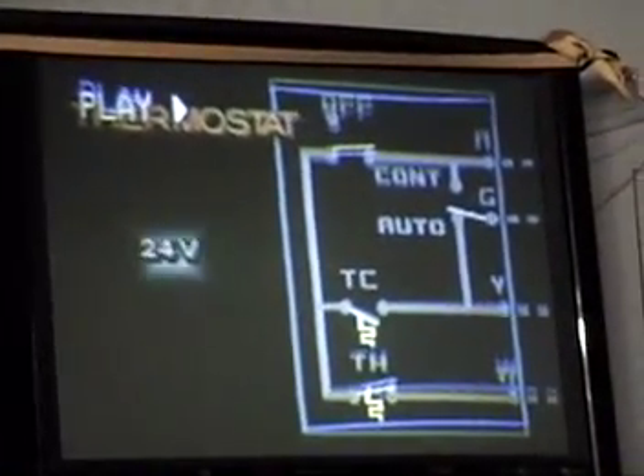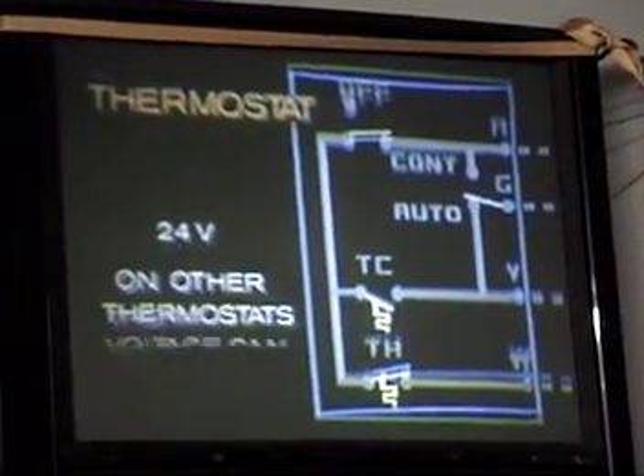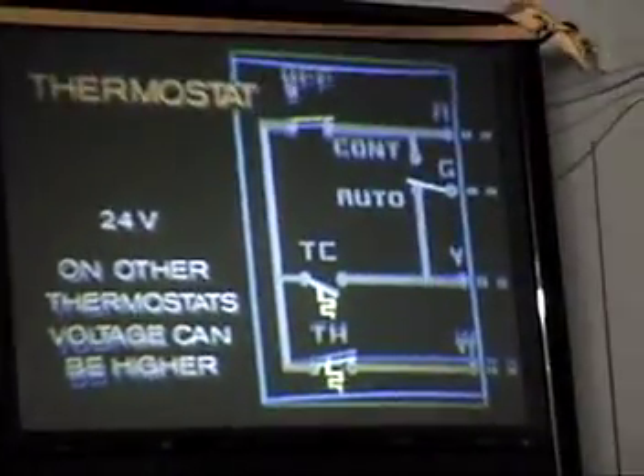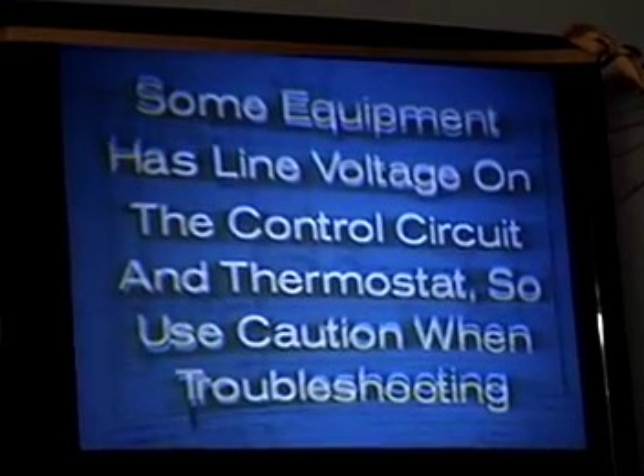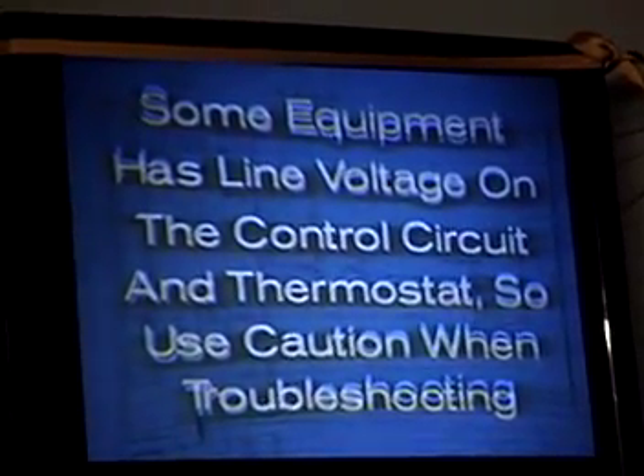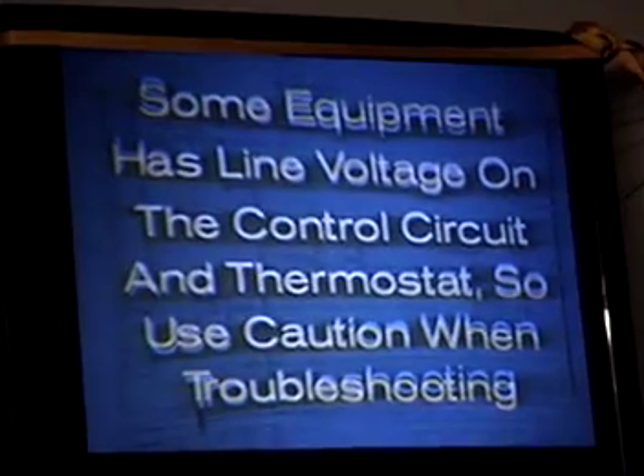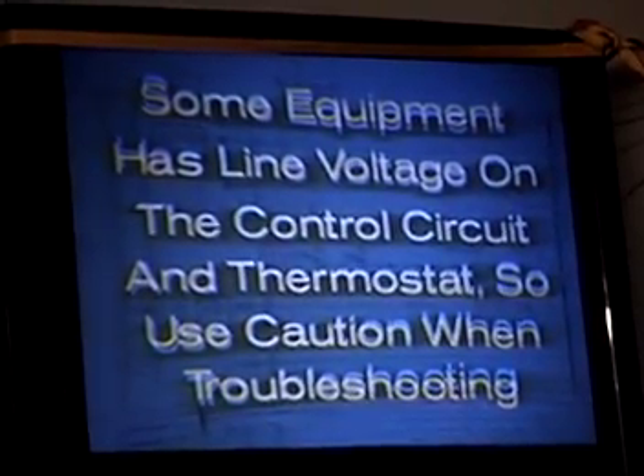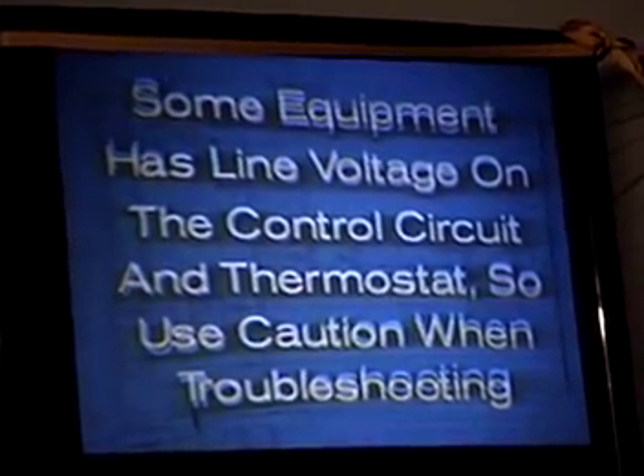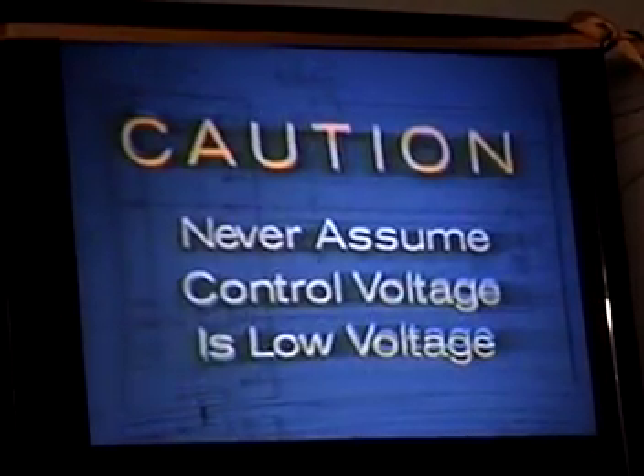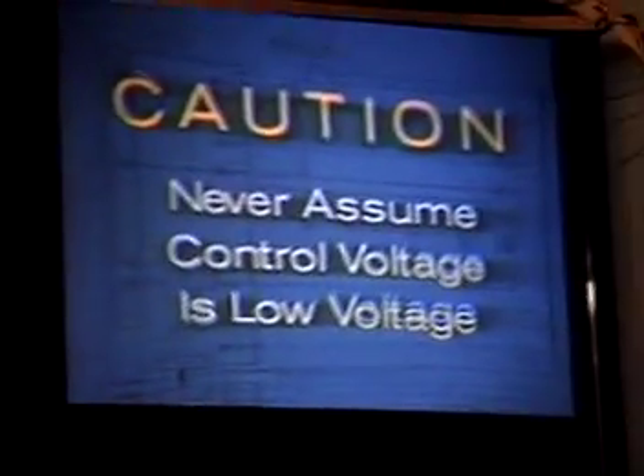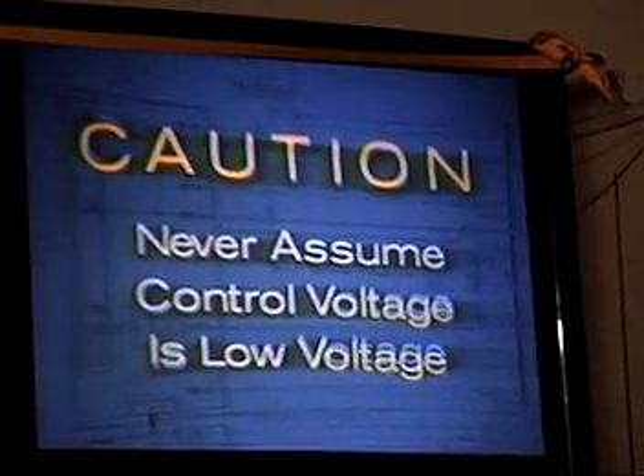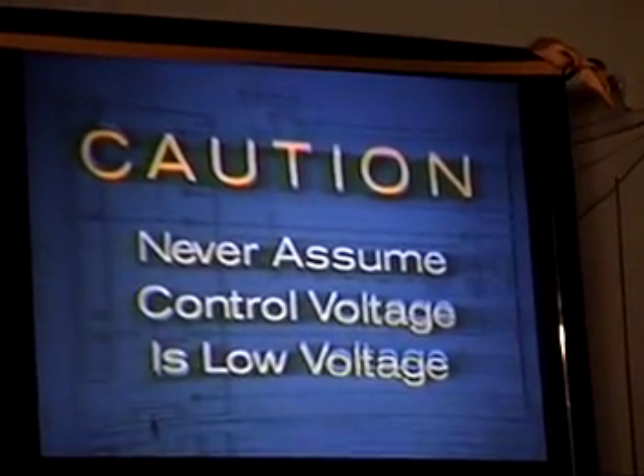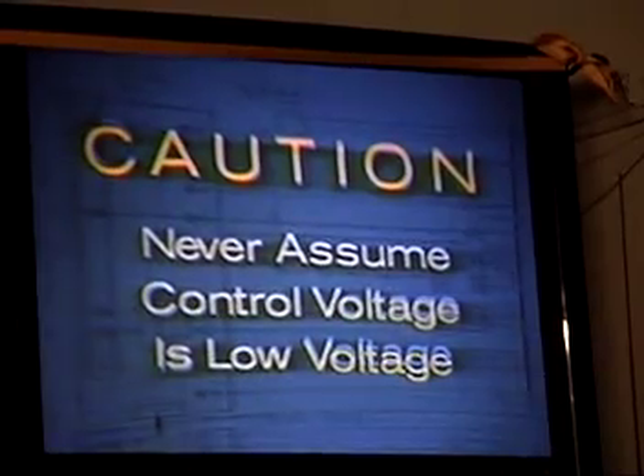The thermostat, in our example, operates on 24 volts, but it could also operate on higher voltage. Some large units have 2 control circuits with varying voltages. Many have transformers with various voltages for electronic circuit feeds. Other units may use the same voltage for power and for control and for the thermostat voltage. Never assume that a control component or wire is low voltage. Any wire or component can have high voltage on it and can be capable of causing fatal injury.